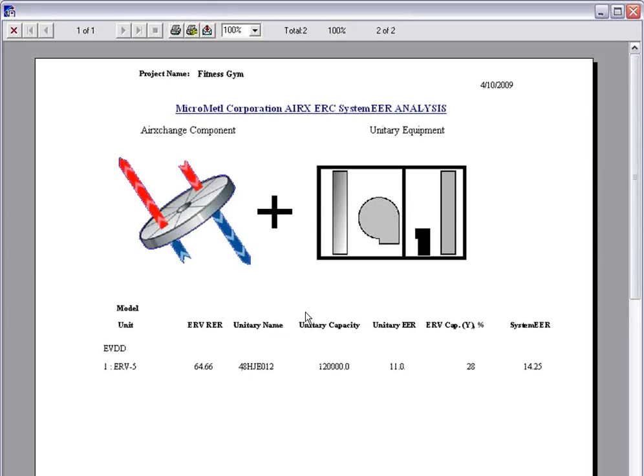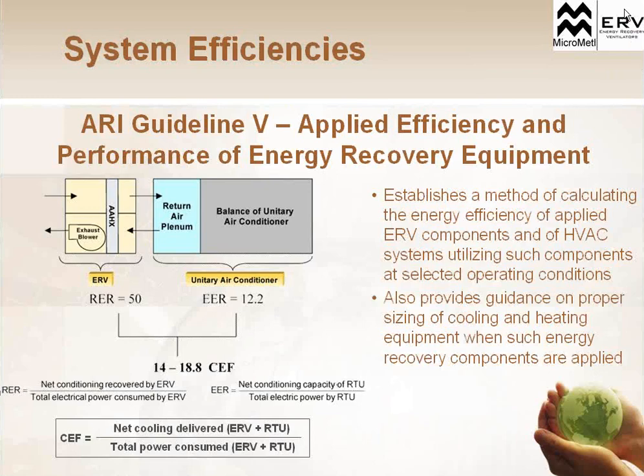Once we get those two pieces of equipment, we can add on the unit itself, the HVAC system, and get a combined efficiency. We can get a system EER on the air exchange component with the cabinet plus the unitary piece of HVAC equipment as well. So we can combine all those pieces and get a combined system EER. There's different system ratings for all these combined pieces of equipment. We have ARI Guideline 5, which actually gives the outline of how to rate these combined efficiencies. So it's applied efficiencies and performance of ERV equipment.